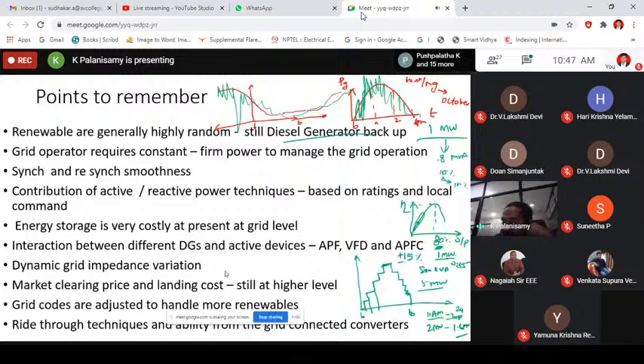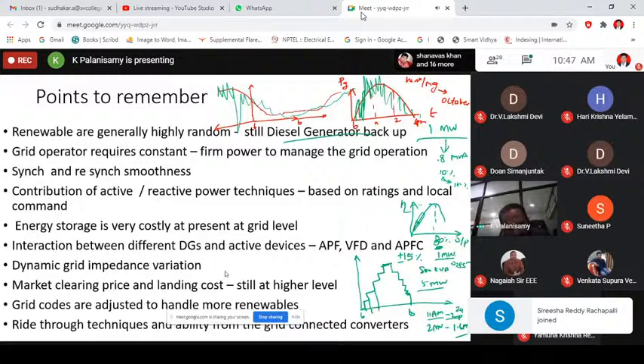If the system provider, that means the active power filter provider, is not measuring it properly for my system, and supplies something else, it may not operate properly with my system condition. Because when you bring an active power filter in parallel with the other loads, of course to the grid, the grid impedance will vary. There is a source, let us say the entire grid as a source, and in parallel to the source we are bringing the active power filter. So there will be a combination of source impedance and active power filter impedance.